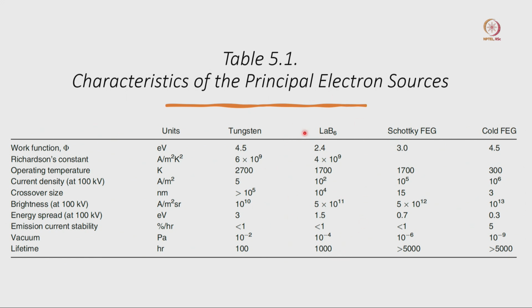For normal room temperature TEM we mostly use the LaB6 filament. That LaB6 filament gives a good contrast, and we can use any kind of electron dose. One more thing we have to remember, for the cryo sample we cannot use a very strong electron beam, our electron dose will be very limited. So that is the reason contrast will always be poor for the cryo sample, and that is the reason if we use the field emission gun it will always be helpful.